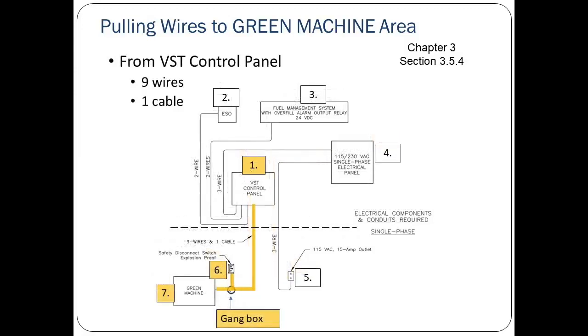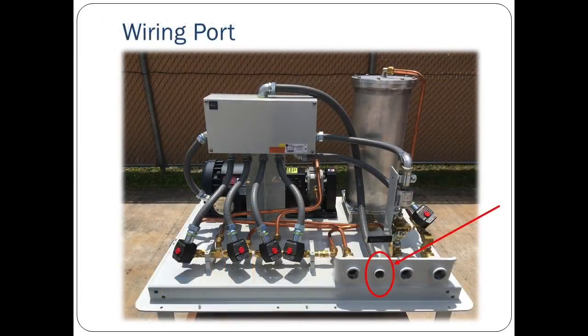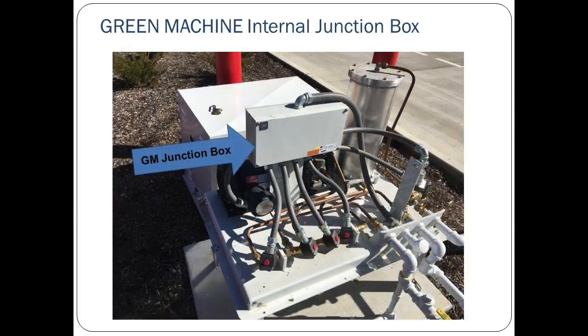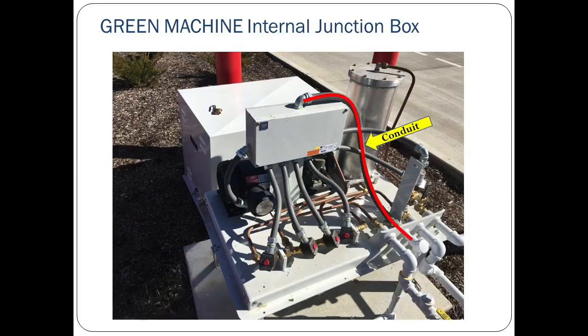The first group of wires that need to be pulled is the group of 9 wires and 1 cable from the VST control panel to the Green Machine and safety disconnect switch. Both the Green Machine functional and safety disconnect subsets of wires are to be run through a gang box. These wires should all be pulled through the wiring port, which is the port located second from the left on the outside of the Green Machine. This picture shows the internal junction box on the Green Machine. The wires that are pulled from the VST control panel must be pulled to the internal junction box through the conduit, which is highlighted in red, from the electrical port on the outside of the Green Machine. Of the 4 ports on the exterior of the Green Machine, the electrical port is located second from the left.